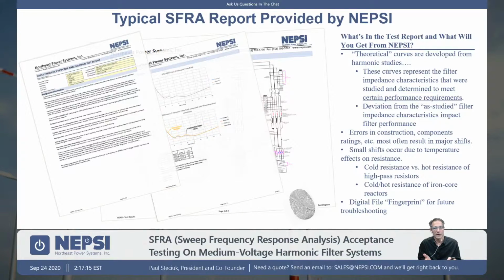Well, the best way to determine the health of that harmonic filter system, if you had the SFRA test done when it was new, will be to call NEPSI and say, hey, I need that digital file. I need the actual digital file. You send somebody out in the field and you redo the SFRA test on the equipment and you confirm: has my wave shape changed? Has my impedance scan changed? If it has changed, you will see it. So we say, put a fingerprint on your design. It's going to be an exact characteristic. If anything has changed, you're going to be able to identify that change with the SFRA test set.